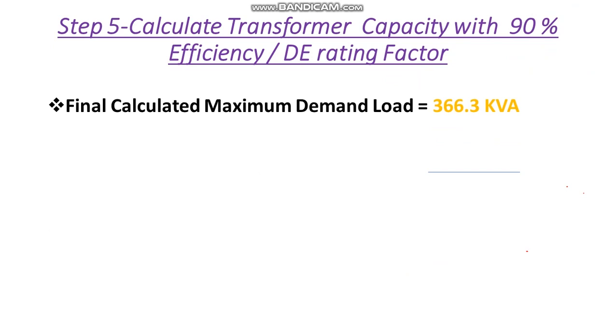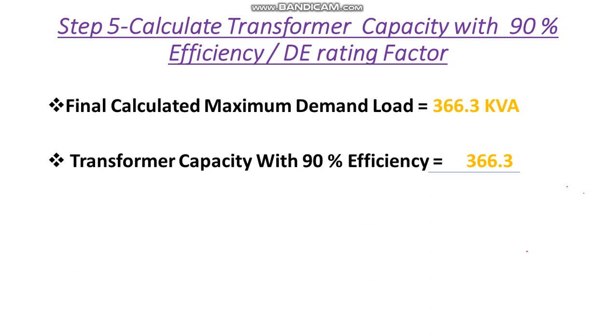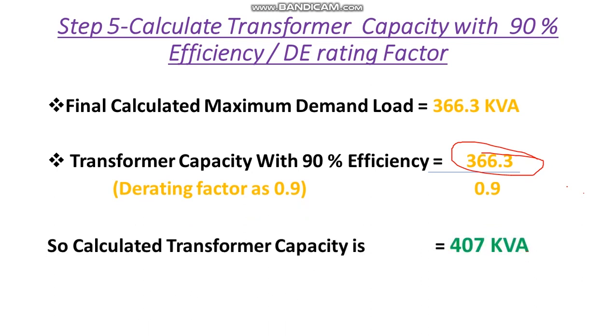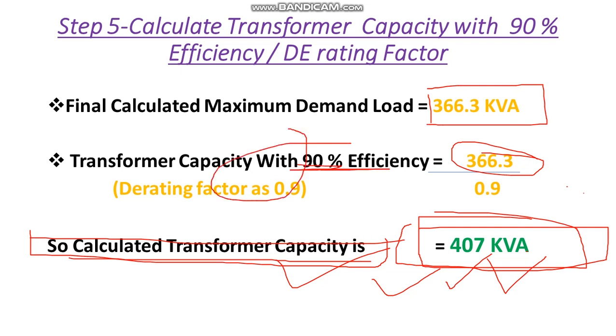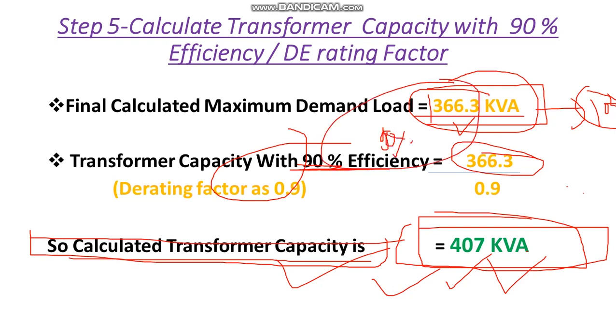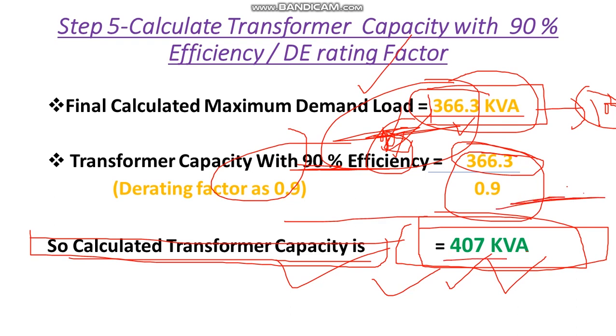Our calculated maximum demand load is 366.3 kVA. We divide this by the derating factor of 0.9 to get the required transformer capacity: 366.3 ÷ 0.9 = 407 kVA. This is the final calculated transformer size. If we had selected based only on the maximum demand load without applying the derating factor, we would not be able to properly connect that load because we should only load the transformer to 90% of its rating.